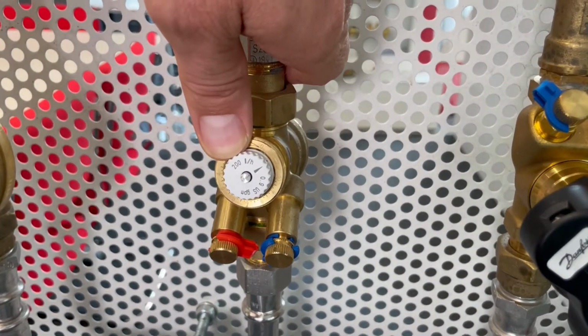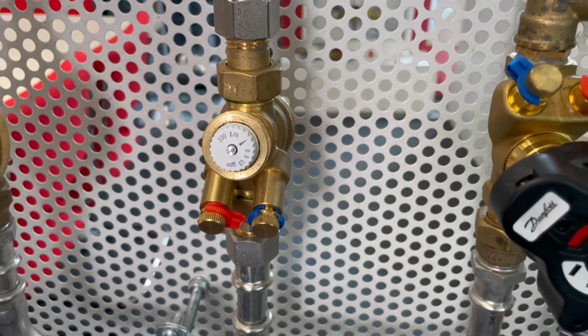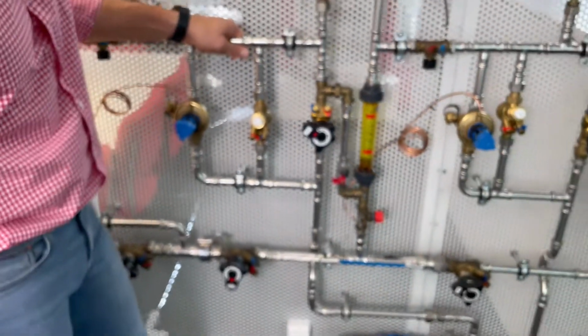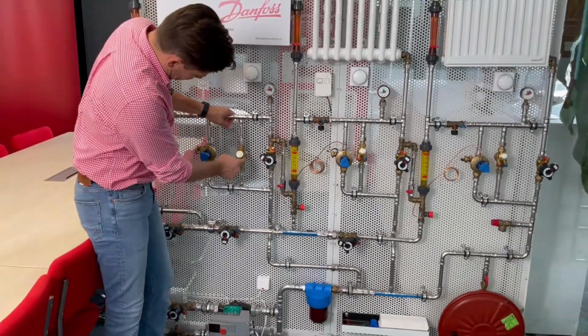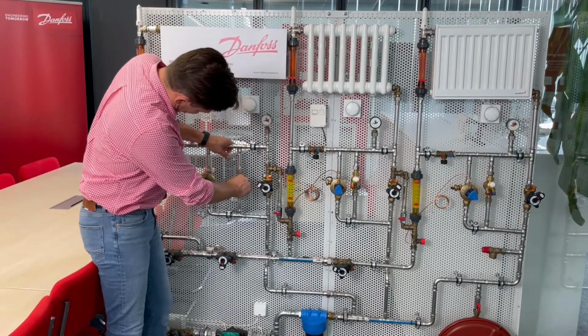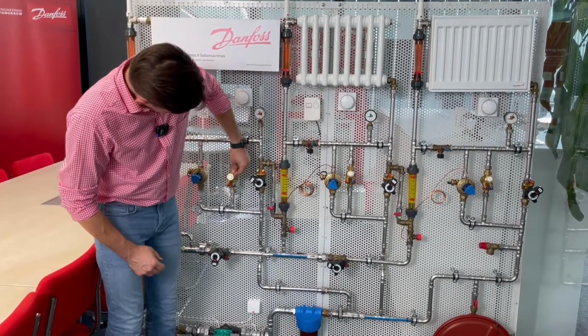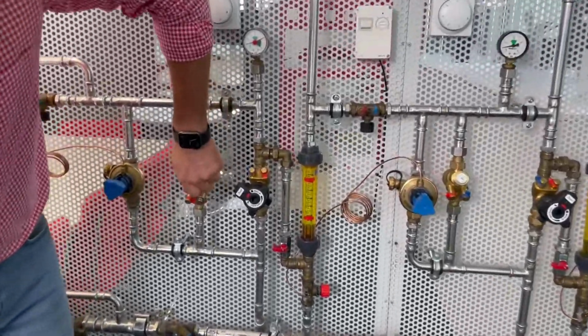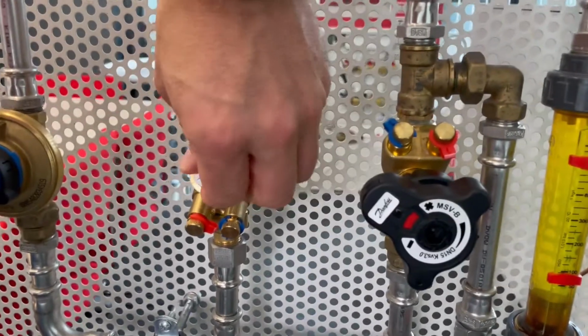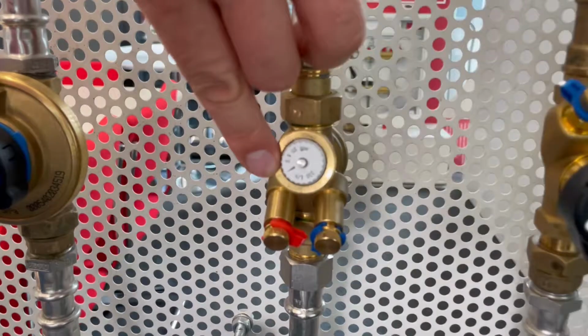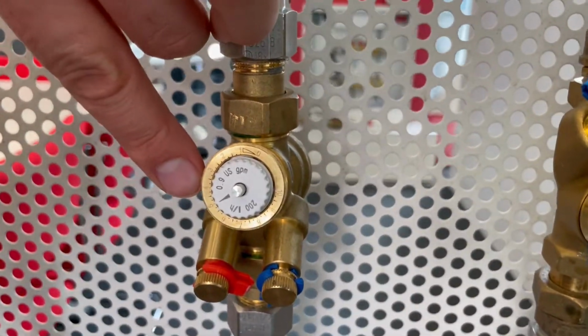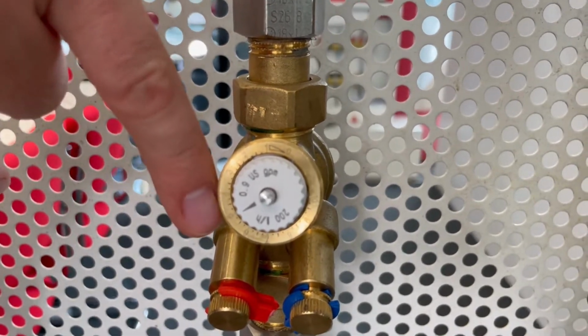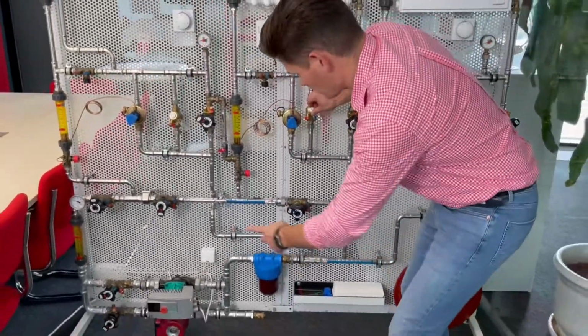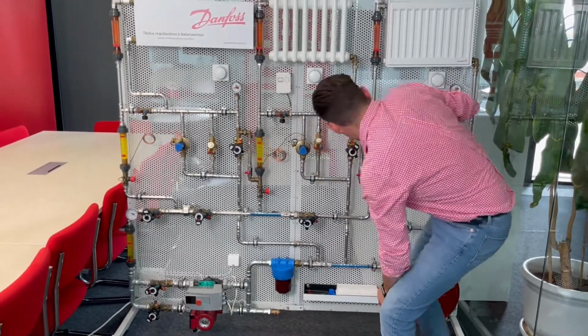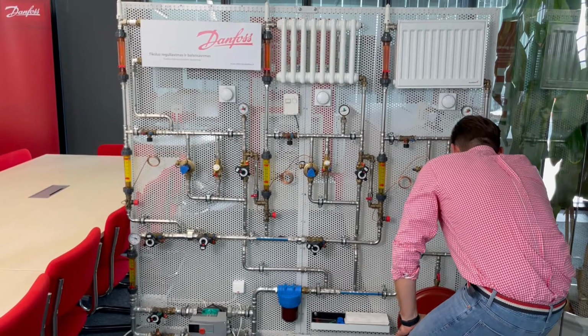200 liters we have maximum. So this is the maximum flow. What can this kind of valve maintain? At setting 0 it is of course closed, but at setting 10 it would have 200 liters, and at setting 5 it would have 100 liters. So I set setting 5. I don't know, is it visible here? Probably it is visible. Yes, setting 5. So I do the same for all risers. Flow is not running because the pumps are now closed. So I set 5 everywhere, and we will see what is happening.